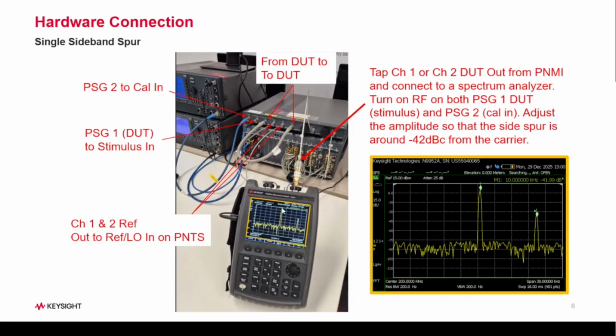I have a spectrum analyzer here. You don't need to use this one. You can use any other spectrum analyzer, as long as you are able to measure the offsets based on what you've set in the measurement definition. So for this case, we are looking at a carrier frequency of about 200 megahertz. So that's where my center frequency is. And I have set an offset of about 10 kilohertz. So using a delta marker, I can say that's 10 kilohertz. And we want to adjust the spur to at least have a 42 dBc gap. It can be lower. So that would wrap up our block diagrams.